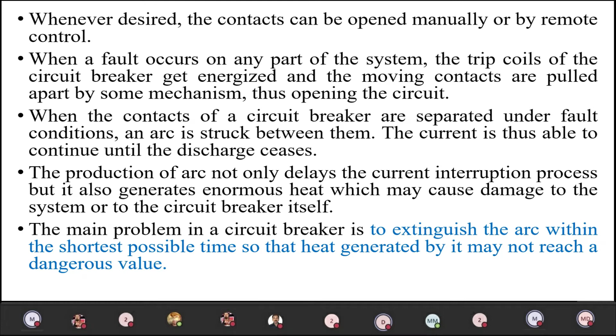Now we will see arc phenomena, that is, how an arc occurs when the moving contact separates away from the fixed contact when a fault or short circuit condition occurs. When a short circuit occurs, a large current flows through the contacts of the circuit breaker before they are opened by the protective system. At the instant when the contacts begin to separate, the contact area decreases rapidly, and a large fault current causes increased current density and hence a rise in temperature.